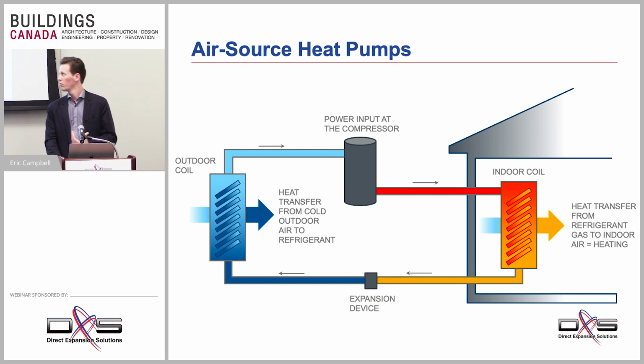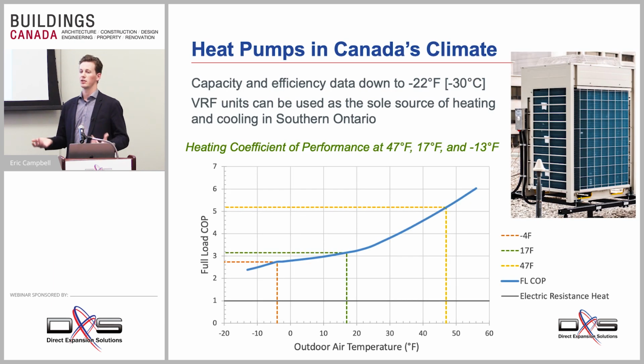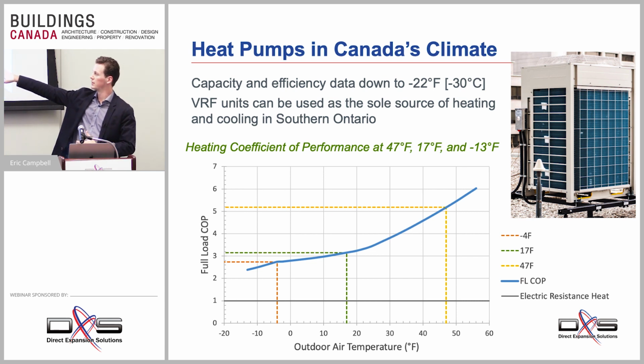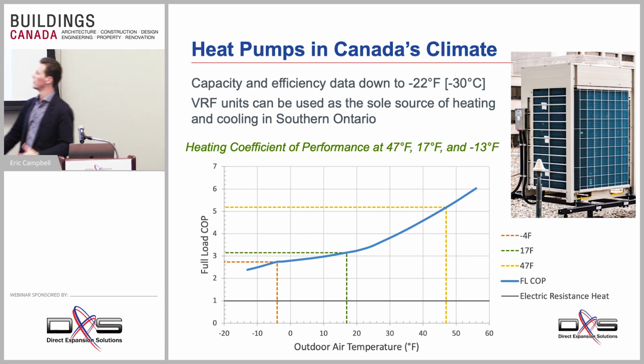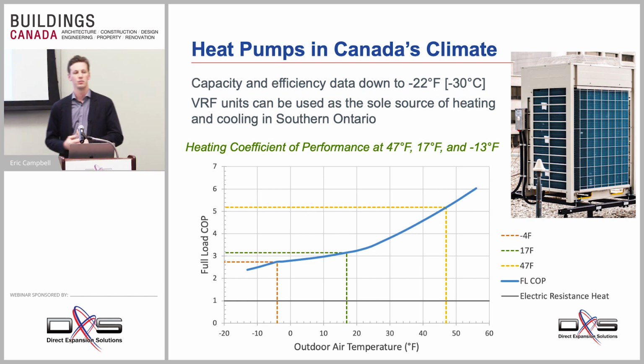And so one of the questions here is, how do you actually do that? If we're using electricity to heat the building effectively, then isn't it the same thing as electric baseboard heat? The reality is, with a heat pump, you're actually able to heat up to 2, 3, or even 4 times as efficiently as you would be able to with electric baseboard heat. That's because we take advantage of what we call the refrigeration cycle in that heat pump cycle. And so we can end up with COPs, in this sort of complicated graph here, showing COPs of around 3, even on our average winter temperatures.